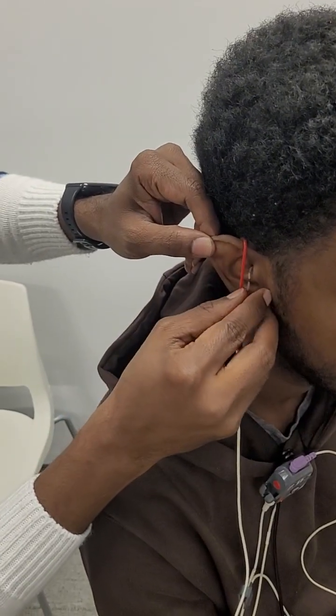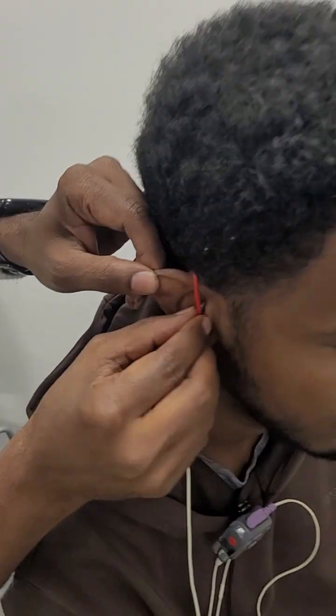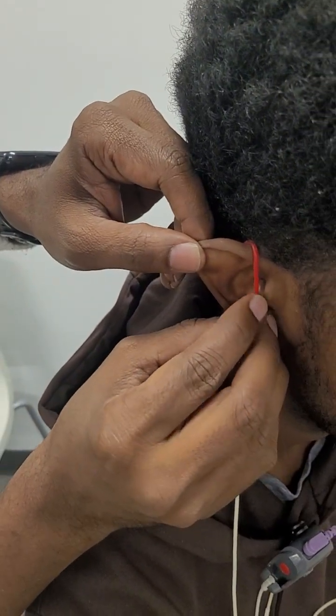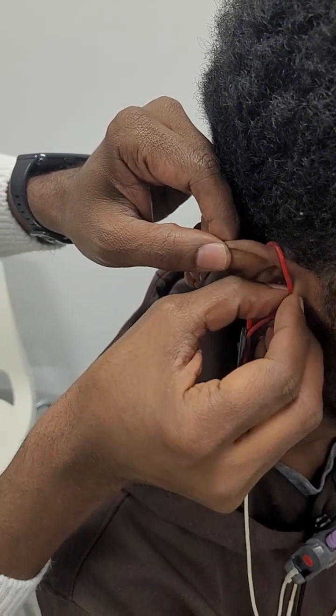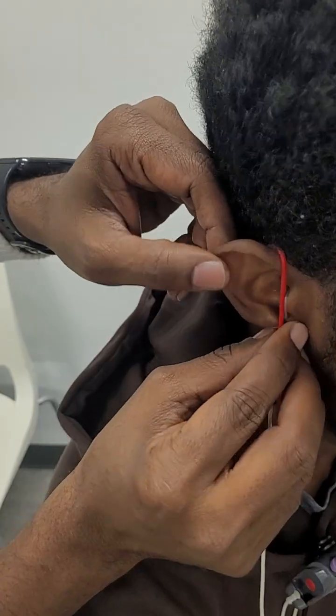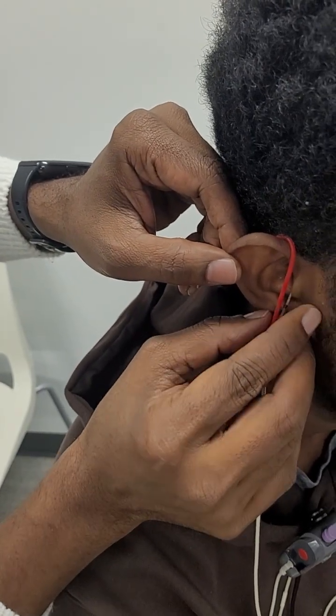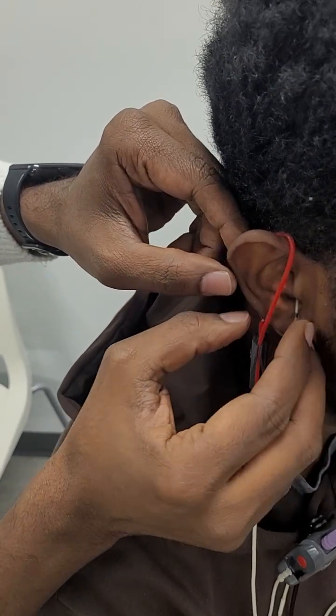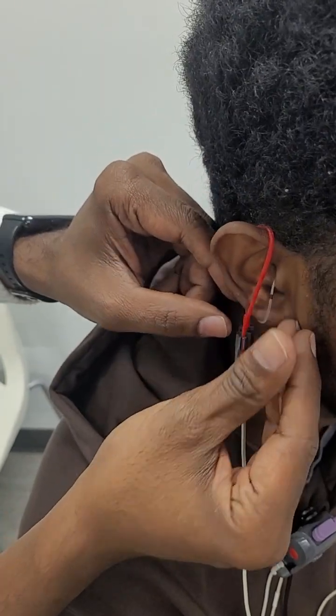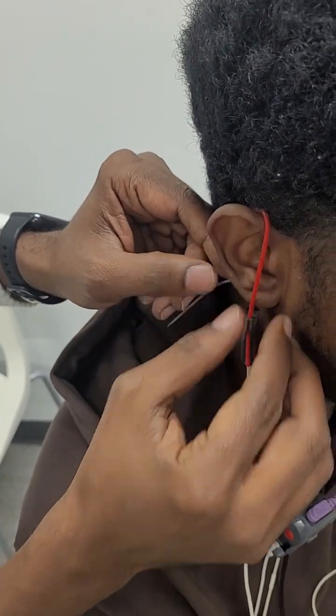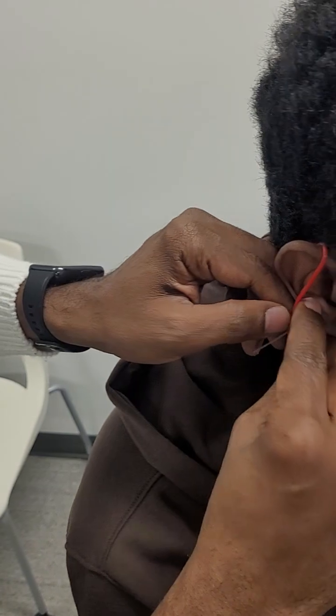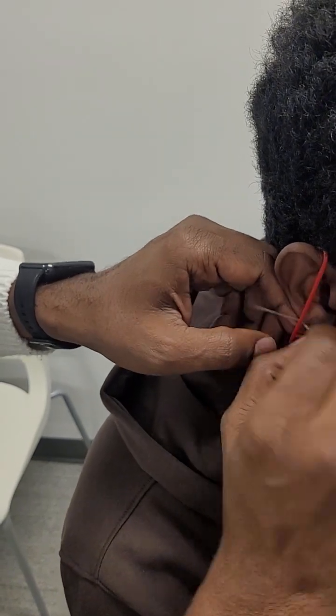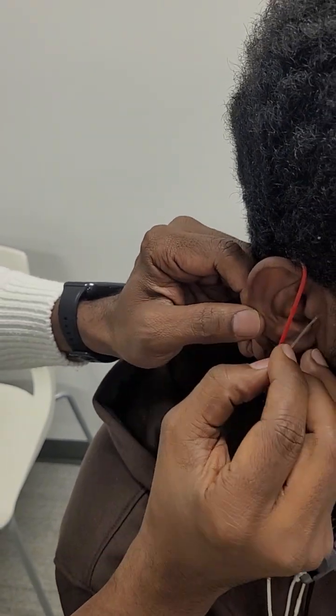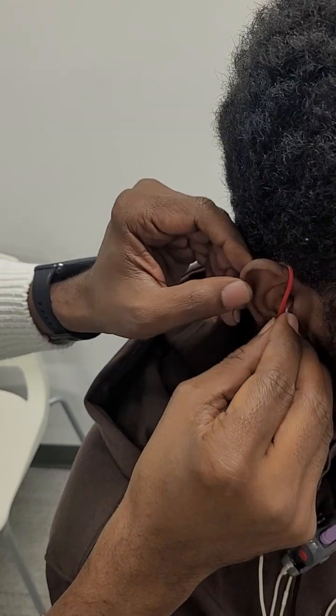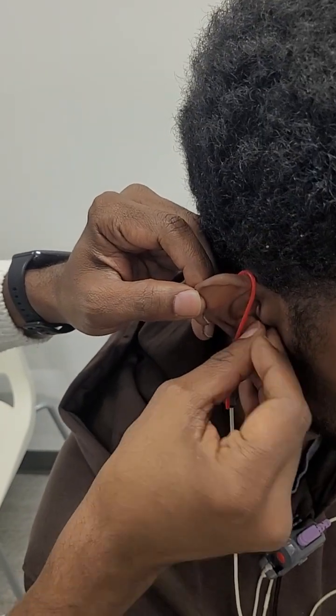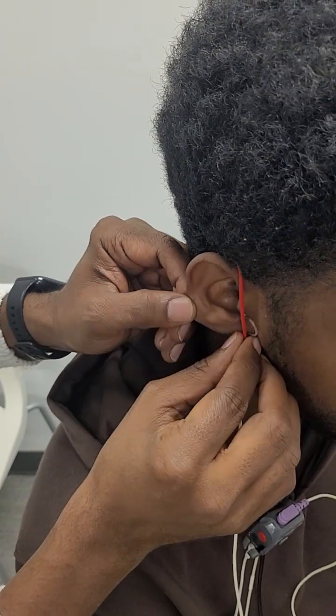So my preset black marking is right in front of the intertragal notch here. This gives me accuracy that it is right in front of the eardrum because it is pre-measured. And as you can see here, the elasticity of the loop itself holds the probe tube in its place, and that also helps me with proper placement. Are you okay? Yeah.